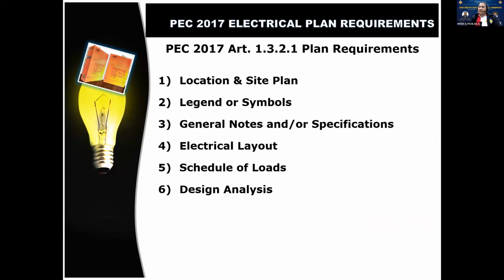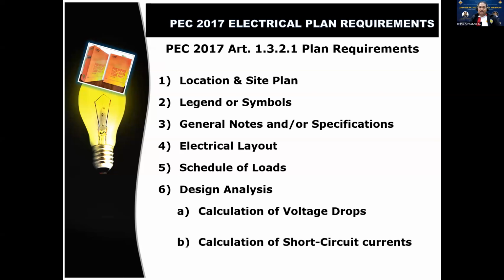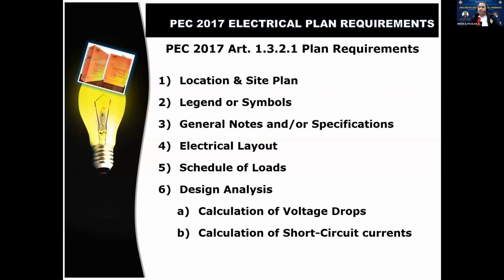And additionally, lately ito yung si design analysis na hindi yan pinag-require noon, but I think last 2015 nagbigay ng memo yung chairman natin doon sa DILG, and cascading to all LGUs natin, OBO LGUs, na additional requirement na yung design analysis, no, yung calculation of voltage drops, no. So together with short circuit calculation, no. So that's why mandatory requirement itong si voltage drop during submission of our design plans.